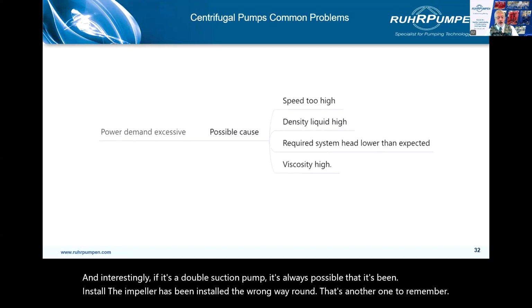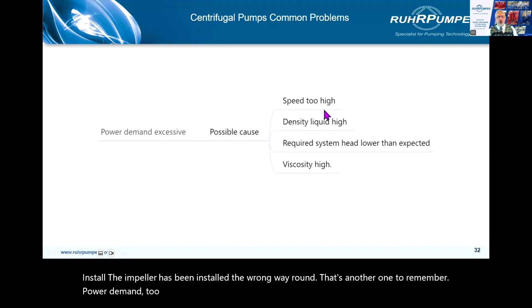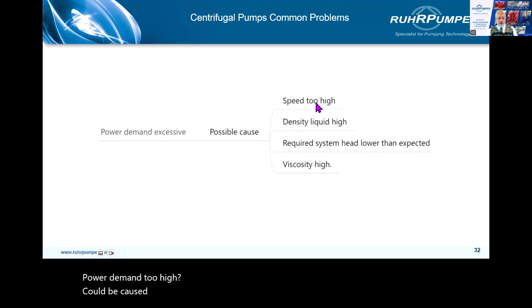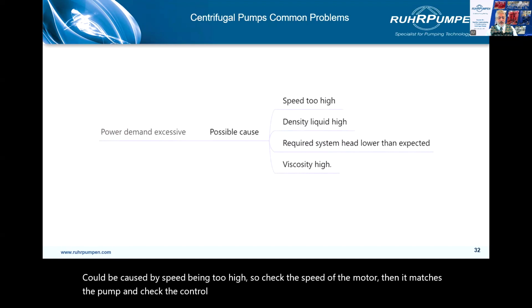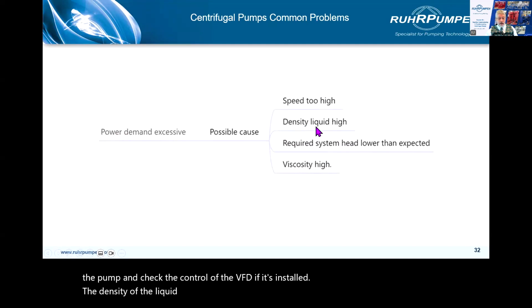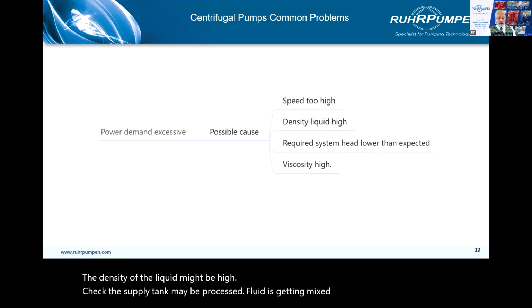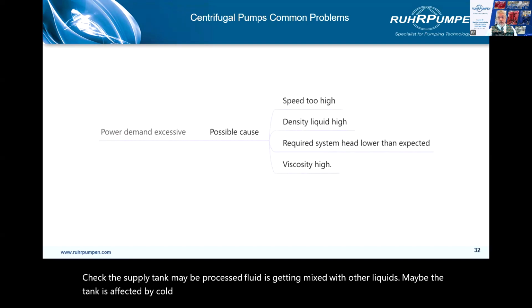Power demand too high could be caused by speed being too high. So check the speed of the motor, that it matches the pump, and check the control of a VFD if it's installed. The density of the liquid might be high. Check the supply tank. Maybe process fluid is getting mixed with other liquids. Maybe the tank is affected by cold temperatures. Maybe there are heaters on the suction tank which aren't operating.